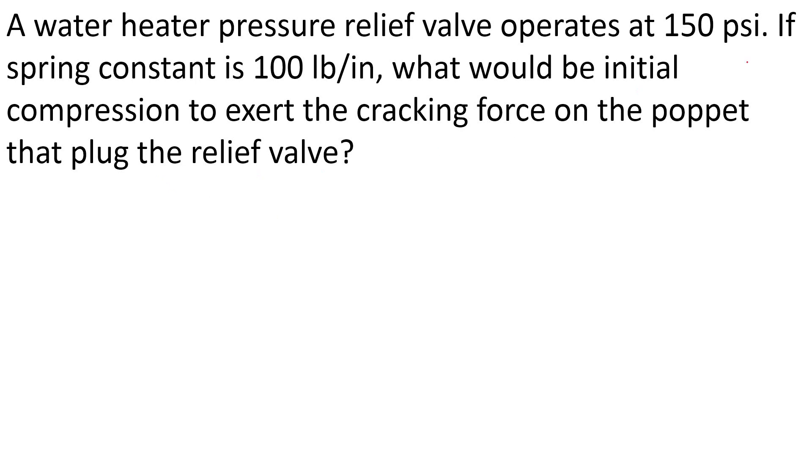In the previous example, we used 150 psi as the cracking pressure. However, it says this operates at 150 psi. Now, if you don't want the water heater to go over 150, then you cannot solve the way we solved the problem in the previous example.